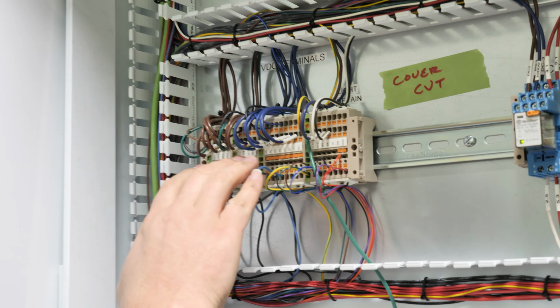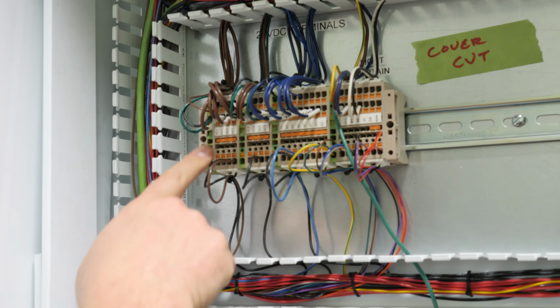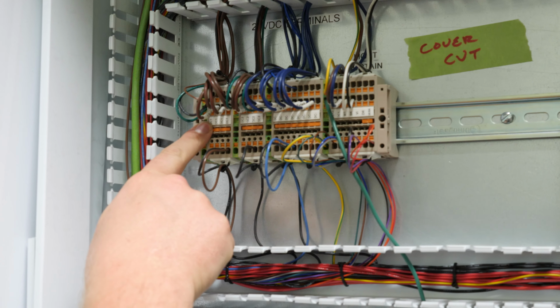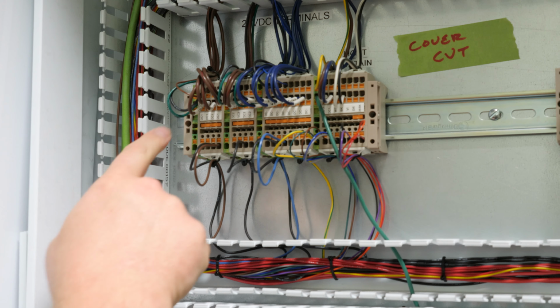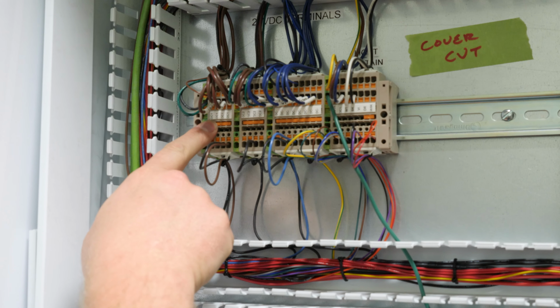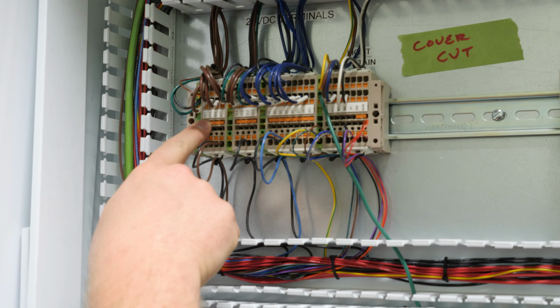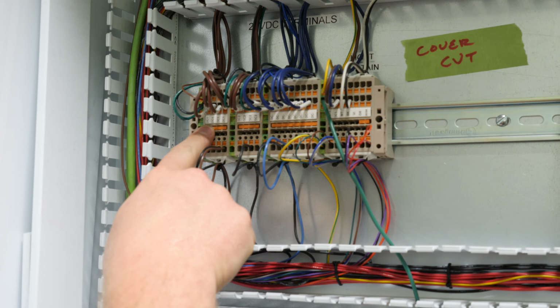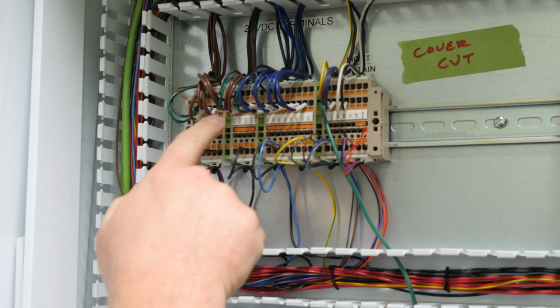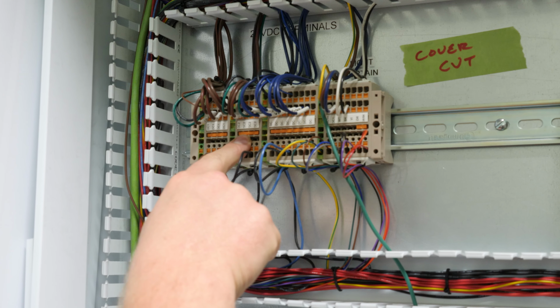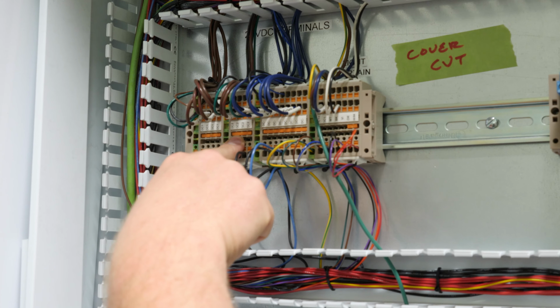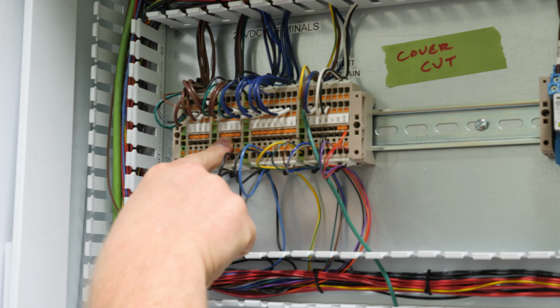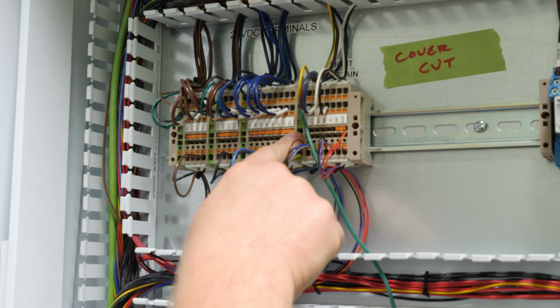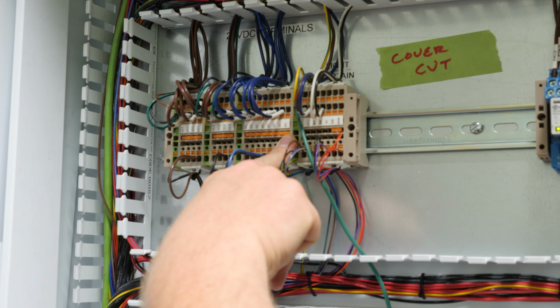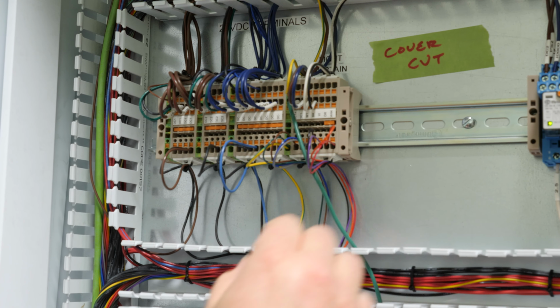Here we have our terminal blocks. We have DC1, which, like I said, that's mainly coming from the PS1. That is going to be all of the computer and monitor and all the main control stuff. Then there's DC2, which is all the secondary, which is going to the servo amps, VFDs, inputs, outputs. All of the DC negatives are all tied together on those. There's not a separate DC negative.